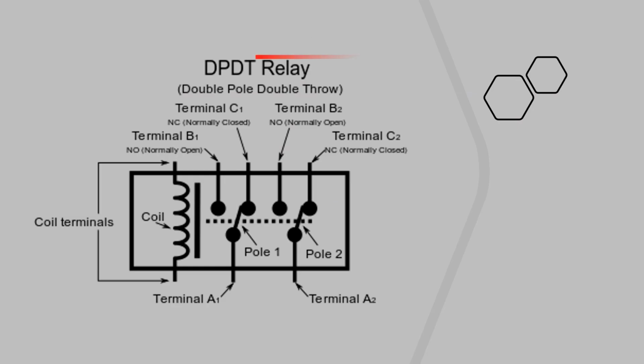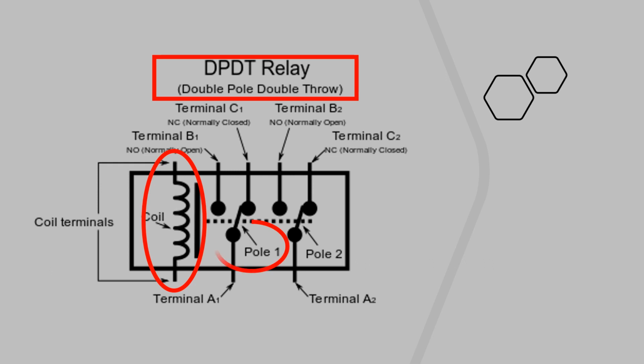In this wiring diagram, we have the diagram for a double pole, double throw relay. This has, of course, the coil once again, which can be 24 volts or high voltage, depending on your application. And it also has two separate sets of contacts that are normally closed, and when this coil is energized, they would open and close the contacts to the other side. So this relay would be used if you have more than one device that you want to isolate or control with a double pole, double throw relay.